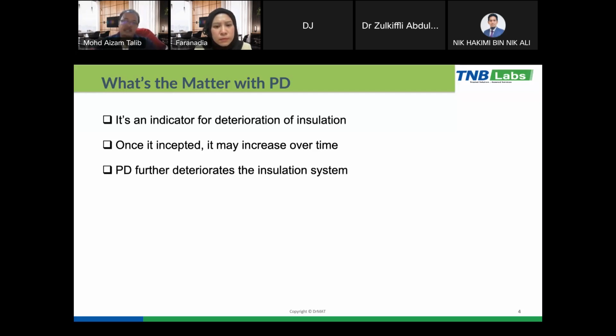Due to the fact that gas has a higher dielectric strength compared to air, we can make our substation design more compact and build the equipment in a small size. During service, the insulation system of the equipment is under the influence of many stresses: thermal, electrical, and environmental. It will be degraded or deteriorated.